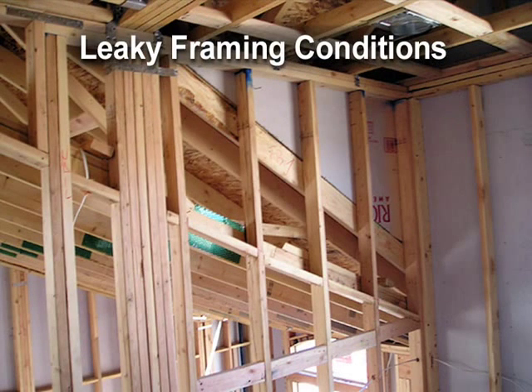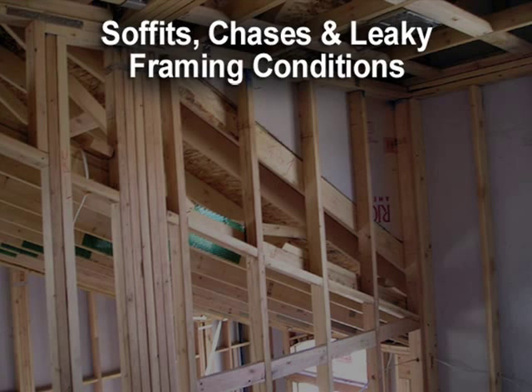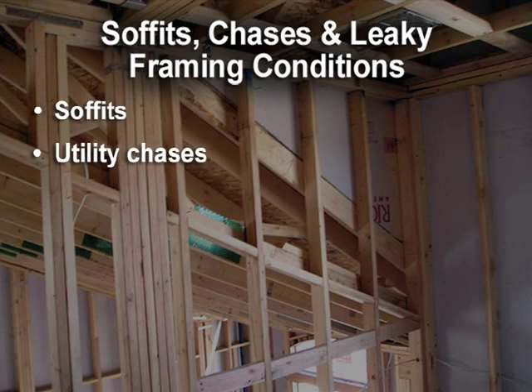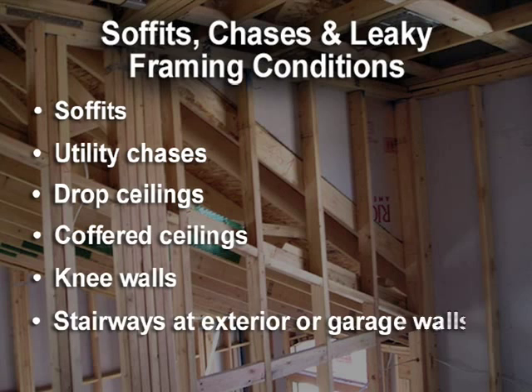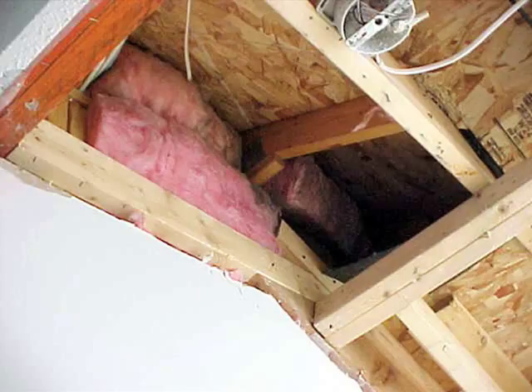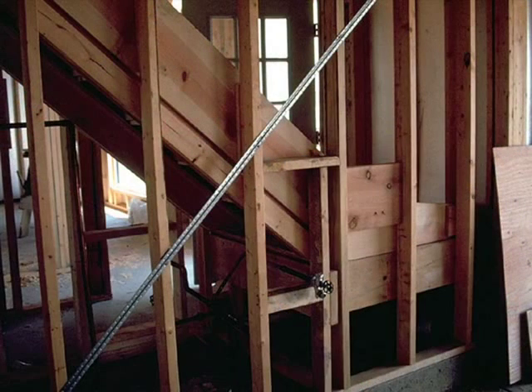Today's home designs have created an increased number of interior framing conditions that can cause very high levels of uncontrolled air leakage. These conditions include soffits, utility chases, dropped ceilings, coffered ceilings, knee walls, and stairways at exterior walls or garage walls. These often are the largest holes in the building shell and are the most difficult to find or seal once the building has been completed. The goal is to plan ahead and look for where these framing conditions may occur, and then to seal them up either prior to or during the framing process.